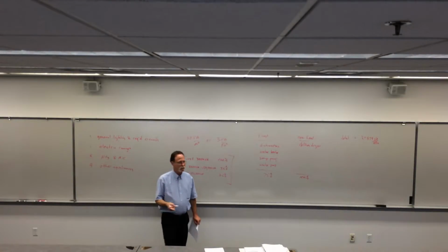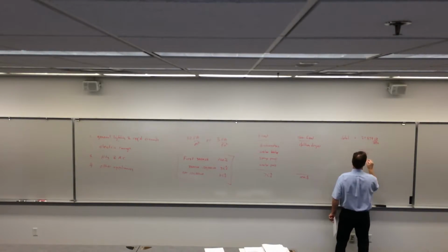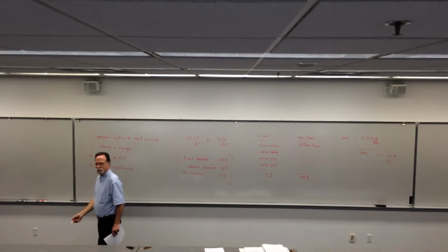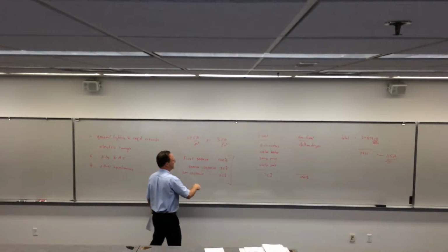What is my service into this building? Well, if the service is 240 volts, I divide into that, and I end up with 115 amps. And that's what I was getting the whole time. How big is my circuit breaker panel for this house? That total was given? Yeah, that total was everything we did over here, all these circuits and all these different appliances. There were numbers for all these in the examples.